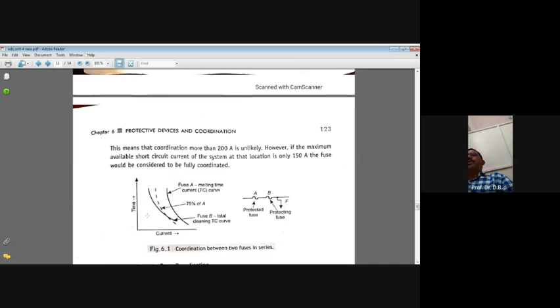Suppose the curves cross at 200 amperes. This means that coordination above 200 amperes is unlikely. However, if the maximum available short circuit current at that location is only 150, the fuses would be considered fully coordinated.